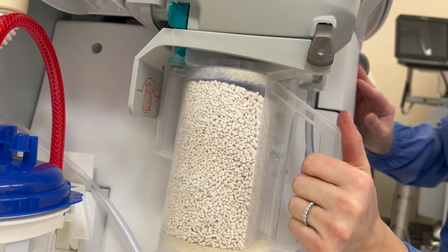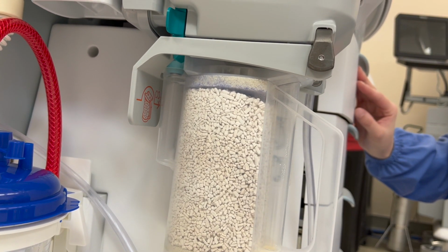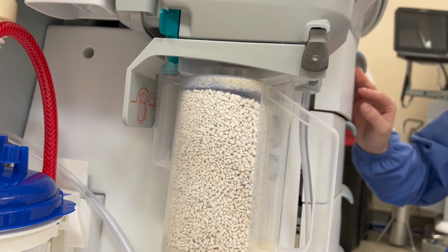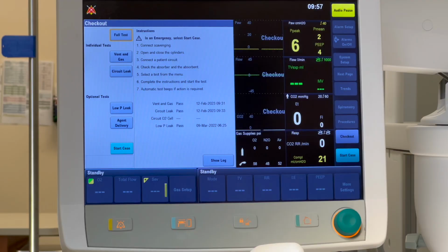ventilate the patient adequately. Typically, you'll know when the CO2 absorber is exhausted based on the color. It typically changes to a violet color, but you should know that this is not always reliable. The degree of change in color can be very slight and you may not notice it. So the best way to know if the CO2 absorber is exhausted is based on the inspiratory CO2 detection on the monitor itself.